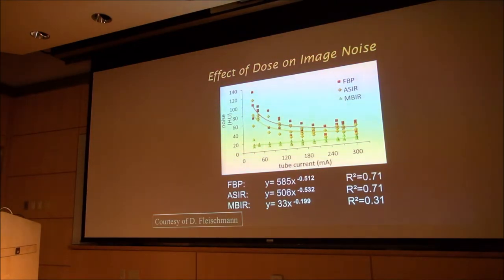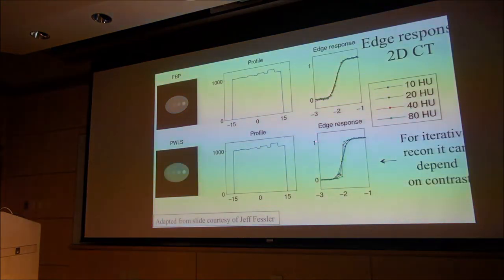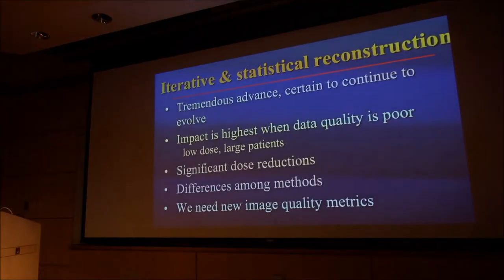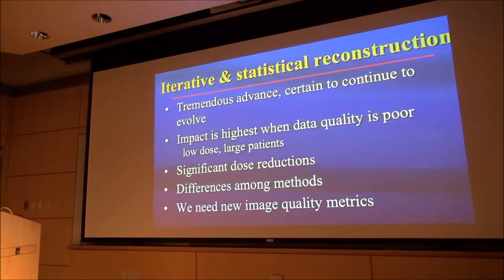What this tells us is noise level and signal to noise ratio no longer tells us anything about information content of a CT image with these non-linear reconstruction methods. The other thing you find is the resolution of a CT system as a fundamental parameter that we can measure, all of a sudden it's not. It depends on the contrast level. These statistical and iterative reconstruction algorithms are a tremendous advance, certain to have an impact. The impact is highest when the data quality is poor. Significant dose reductions can be obtained, although perhaps the manufacturers are trying to oversell them. There's a big difference among methods, and we need new image quality metrics because our old linear system metrics don't work.